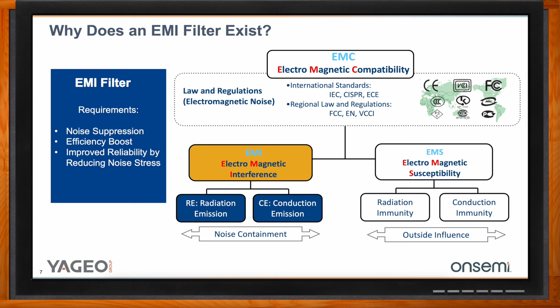The first one would be the differential mode noise. As the name indicates, that is noise that is different on both lines. So you have an AC input with 3 lines going in: one is ground, the other two are the ones we're talking about. If you have noise on those lines that is different from one another, we need to filter that. That's where we use the X capacitors, and X capacitors are connected line to line.